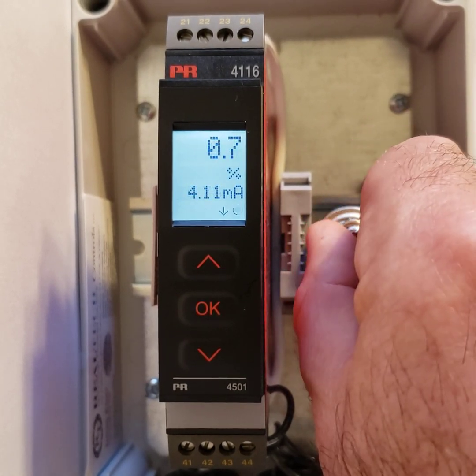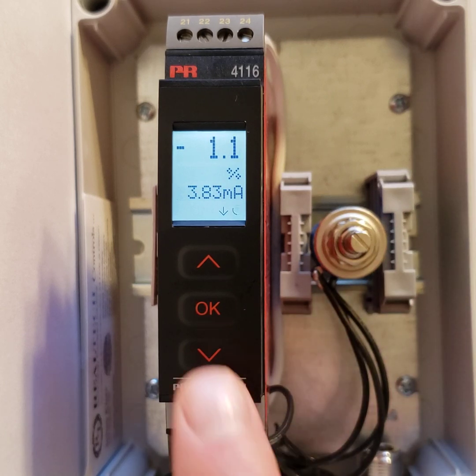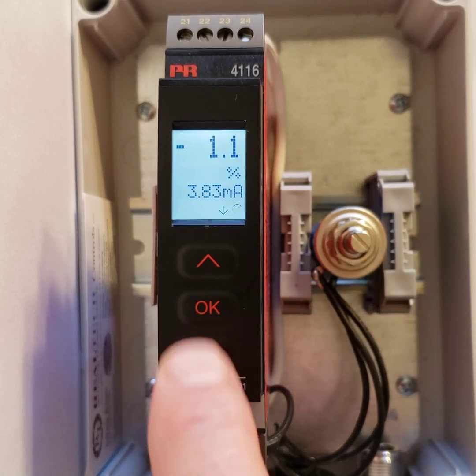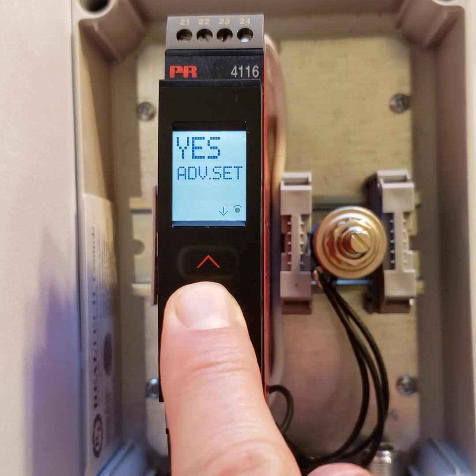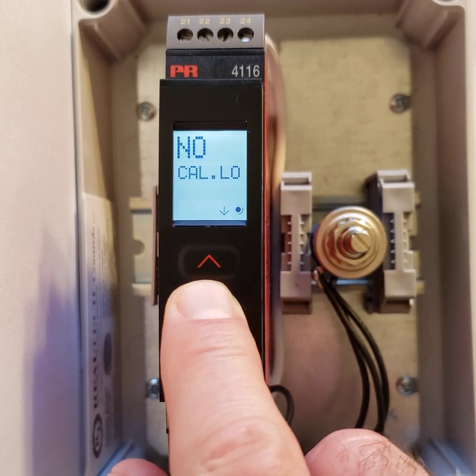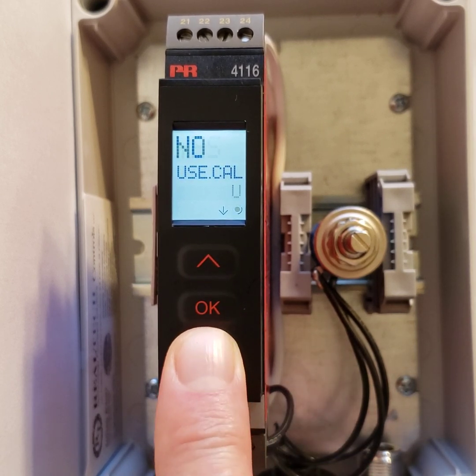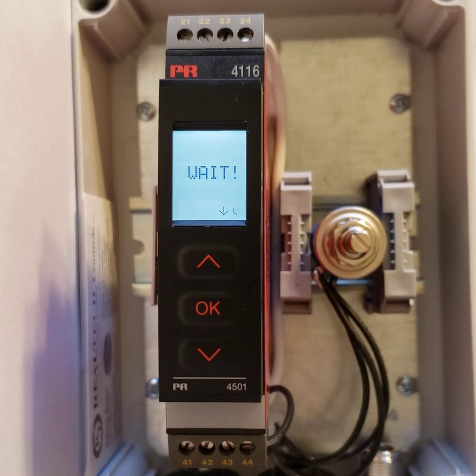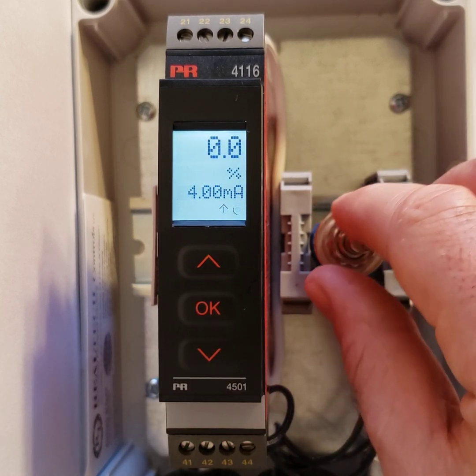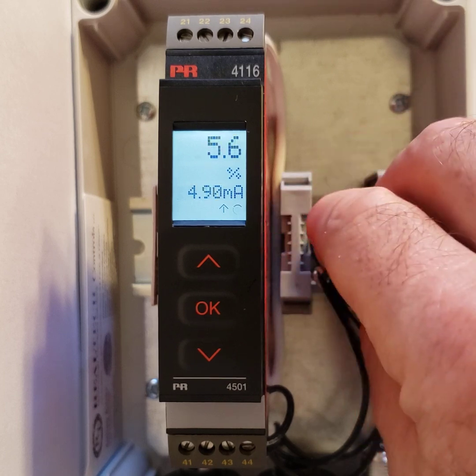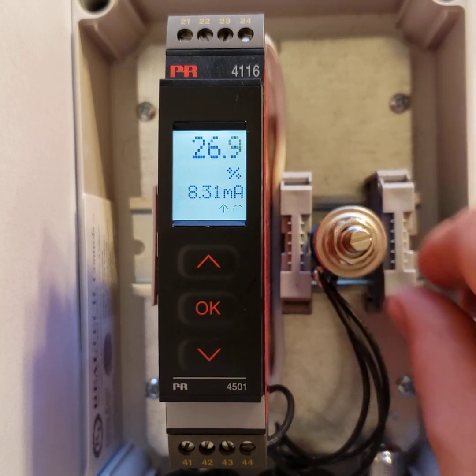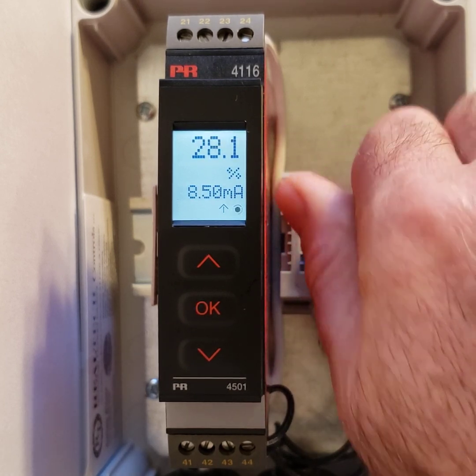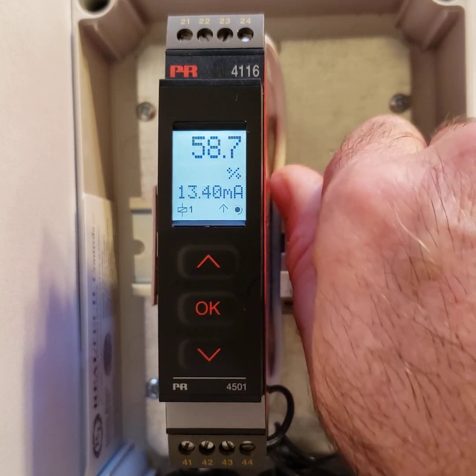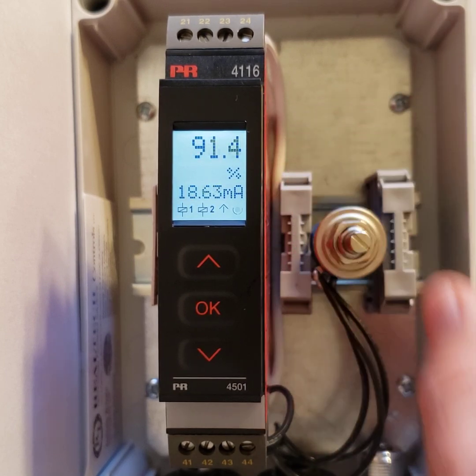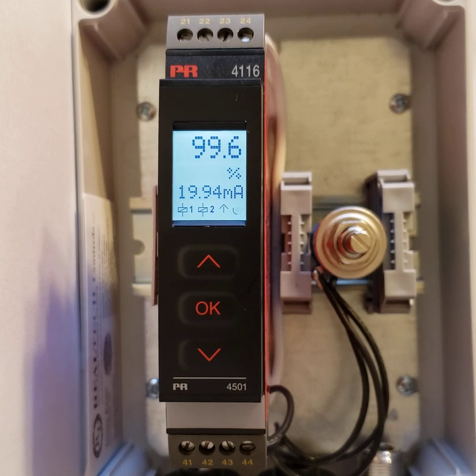If I want to take that calibration away, so say I want a brand new system installed and I don't want the calibration anymore, you can just choose you don't want to use the calibration. And this now resets the calibration or just takes out any high or low values that it's been scaled at. You can see there that that's the original high value of the pot. There we go.